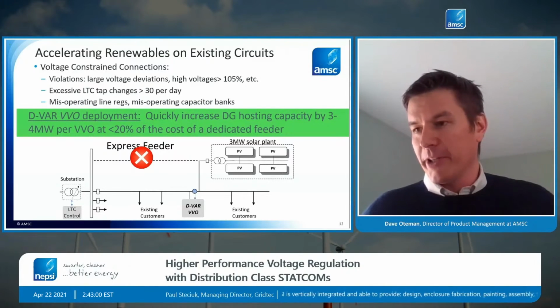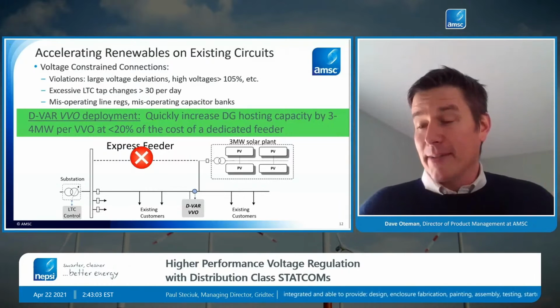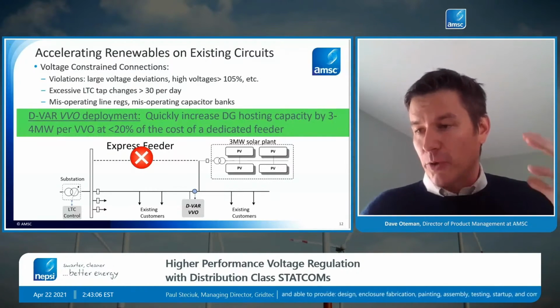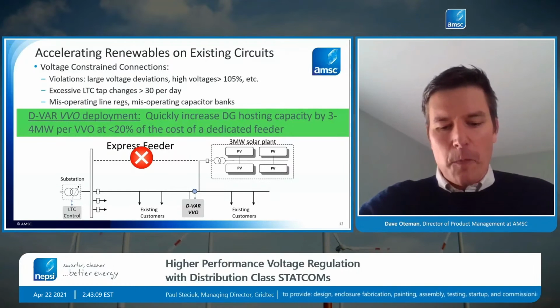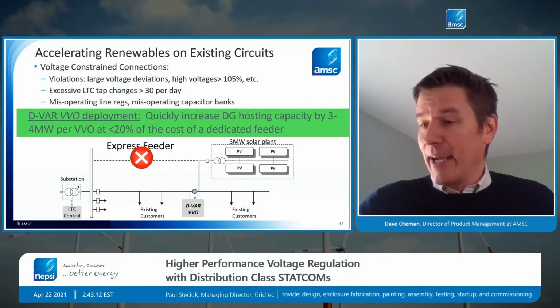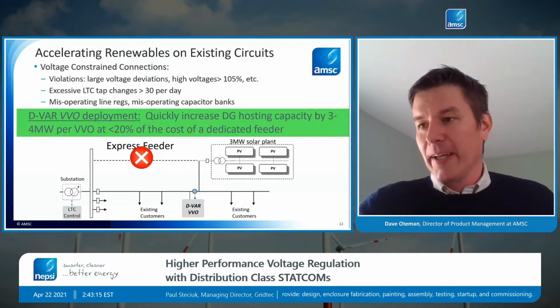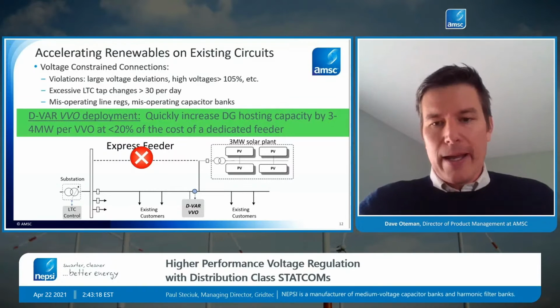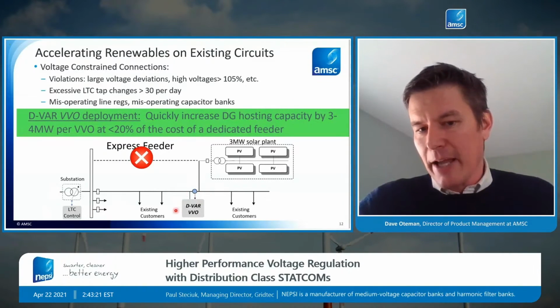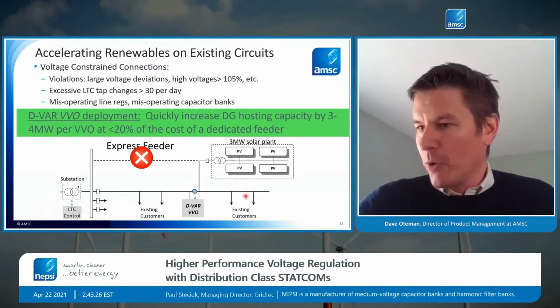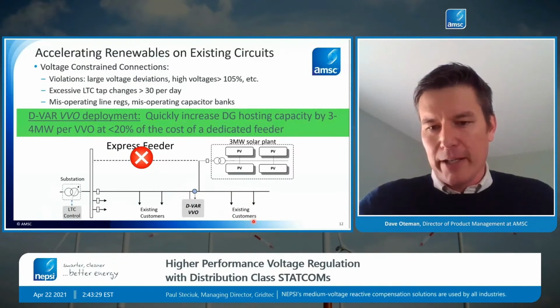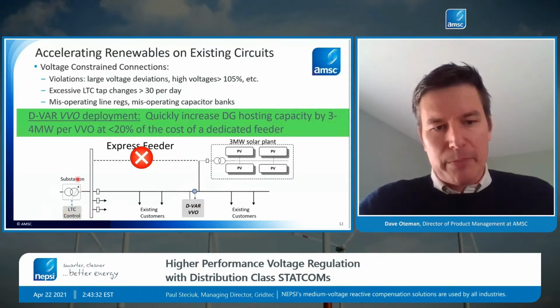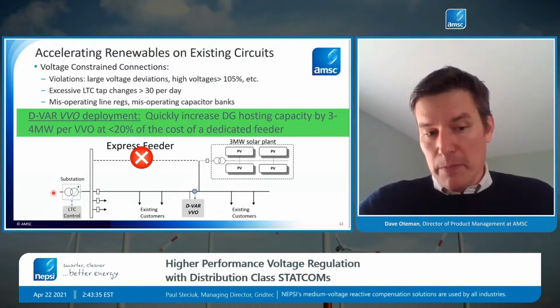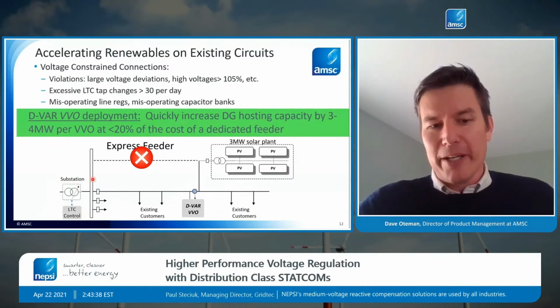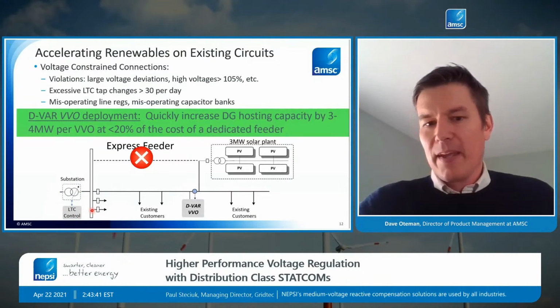We talked about this variability and showed very clearly how existing mechanical assets' lifetime is directly sensitive to it. So utilities have to be sure they're protecting their assets, not wearing them out prematurely as part of these interconnects. That's really where the STATCOM technology is able to address both sides: we're able to protect existing customers from power quality issues like high voltages and aggravating voltage fluctuations, and we're able to protect tapping equipment like load tap changers and line regulators from excessive overoperation.